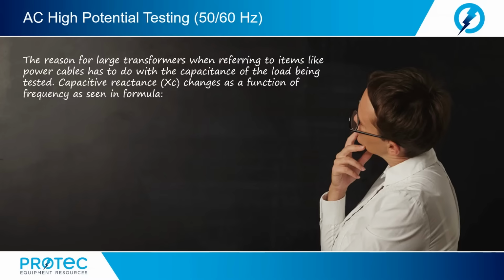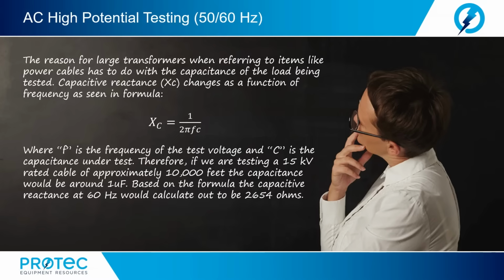All right, well, the reason for large transformers when referring to items like power cables or large rotating machines has to do with the capacitance of the load being tested. Capacitive reactance, or X sub C, changes as a function of frequency, as seen in the formula. Capacitive reactance equals 1 divided by 2 pi F C, where F is the frequency of the test voltage and C is the capacitance of the device under test. Therefore, if we're testing a 15 kV rated cable of approximately 10,000 feet, the capacitance would be around 1 microfarad.